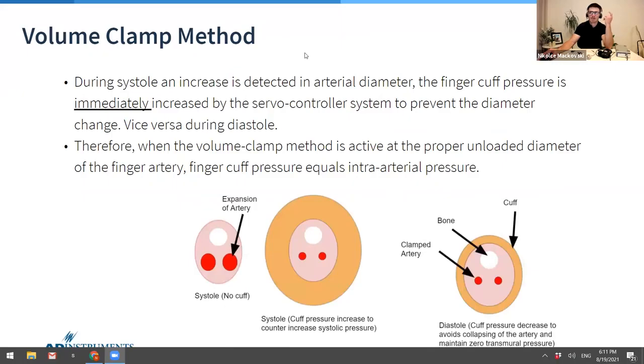You can see here with the volume clamp method, obviously this is a very crude image, that during systole the arteries expand. Here's an image with the cuff around the finger, a cross section. Whatever the pressure is at that point during systole, the cuff will immediately increase via the servo control system to prevent the diameter change, therefore keeping the diameter the same. It's the opposite during diastole. As soon as systole passes and diastole begins, the cuff immediately drops in pressure. That way it prevents the arteries themselves from collapsing. It just wants to keep that diameter the same. The important thing to remember here is that we want the finger cuff pressure to equal the intra-arterial pressure.